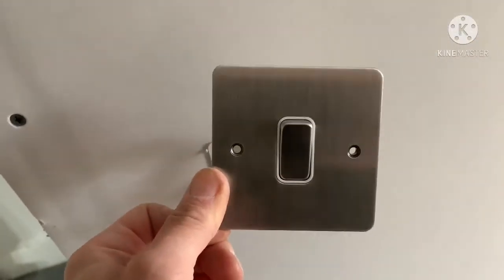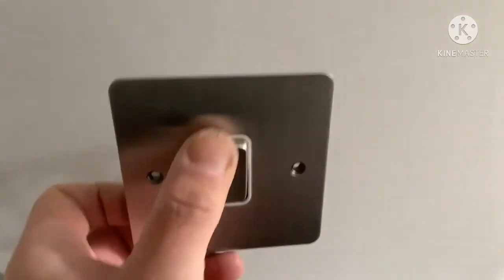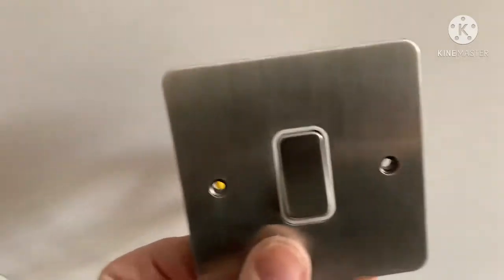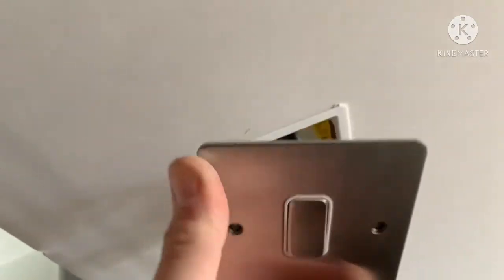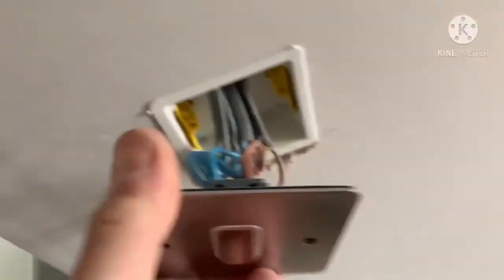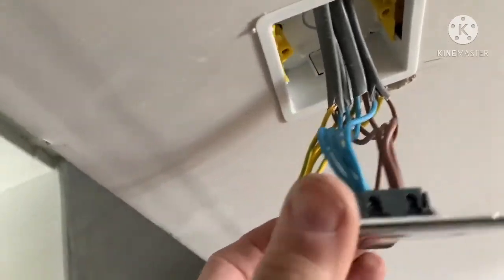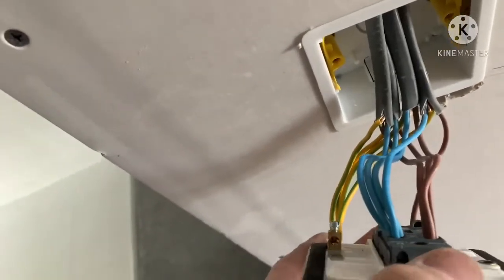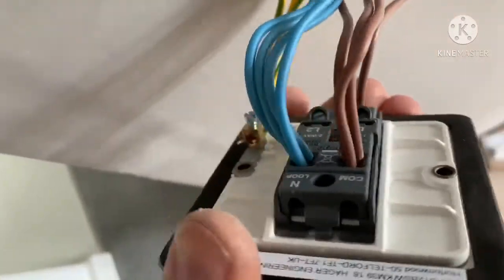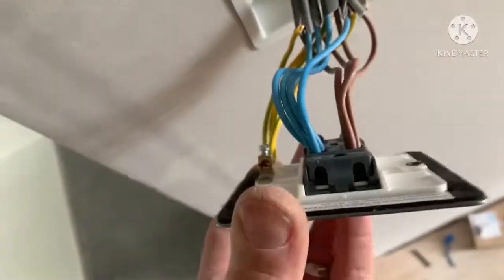These are the accessories going in - the customer has supplied her own. They're made by Hager, the Sollysta range - the brushed chrome flat plate. Really, really nice. Does anybody remember what made MK so good? MK's terminals were always facing up when you were making the switch off, so you didn't have to twist your switches and sockets all the way around. Hager has done the same thing - just a nice touch.